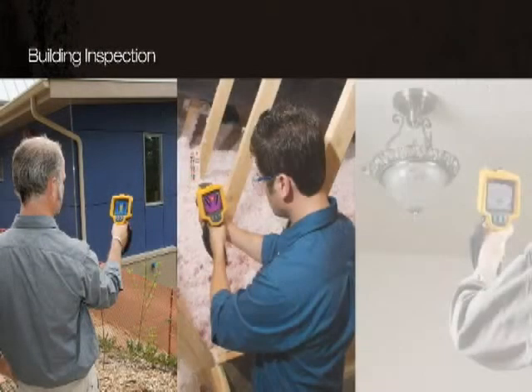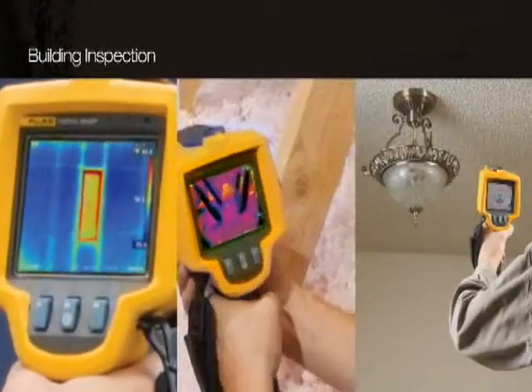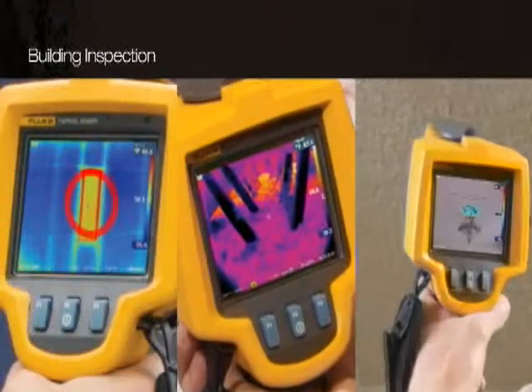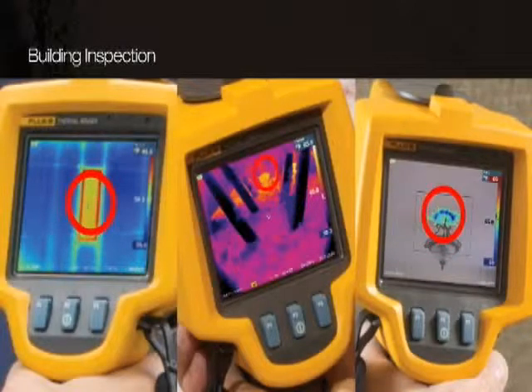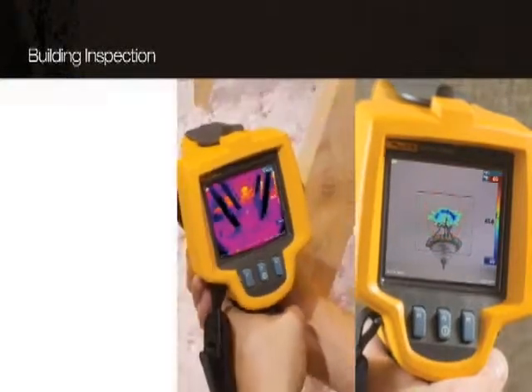A second example might be inspecting a building. Without thermal imaging, air leaks, insulation issues, and moisture are extremely difficult if not impossible to detect. Thermal images will reveal the exact location of issues without the need of time-consuming searches with a moisture meter or drilling and probing to find missing insulation.